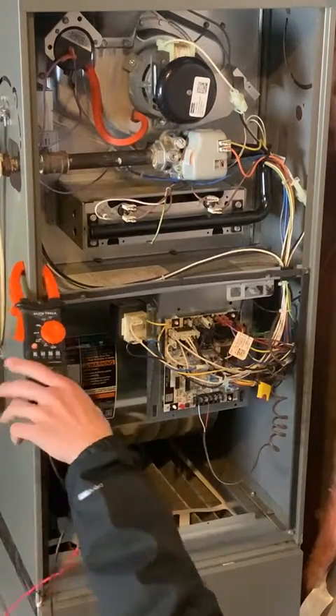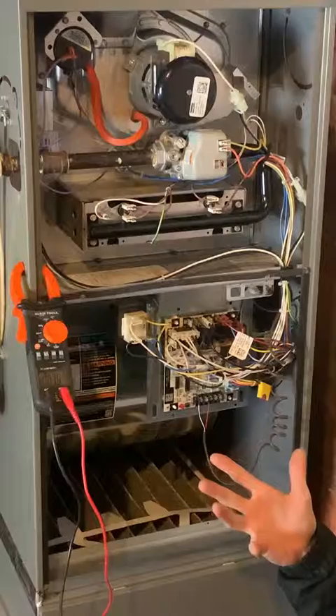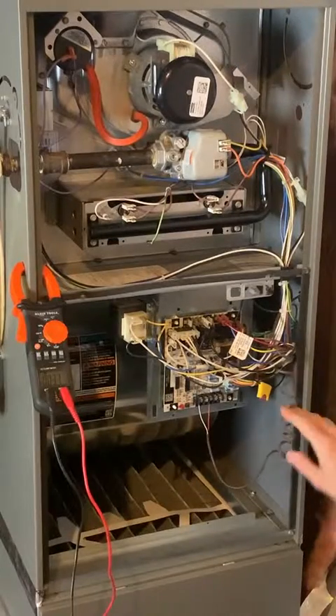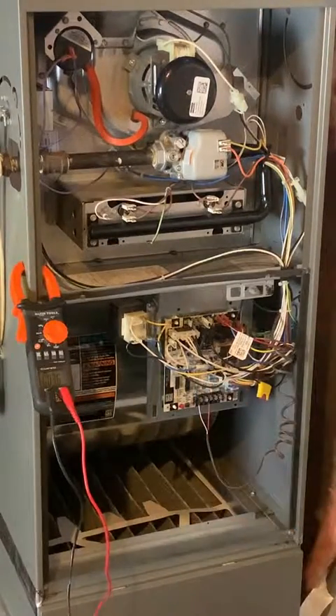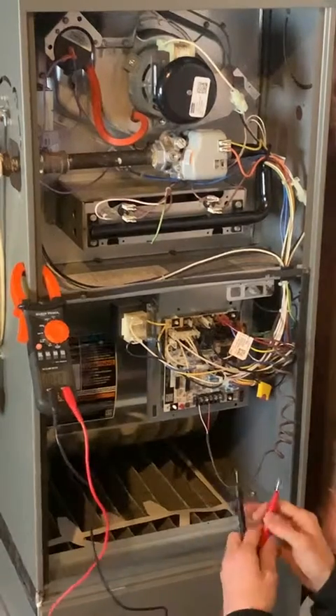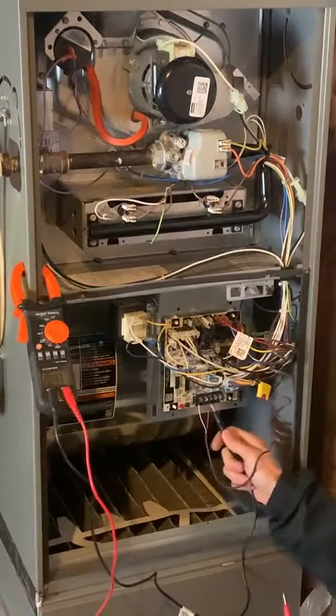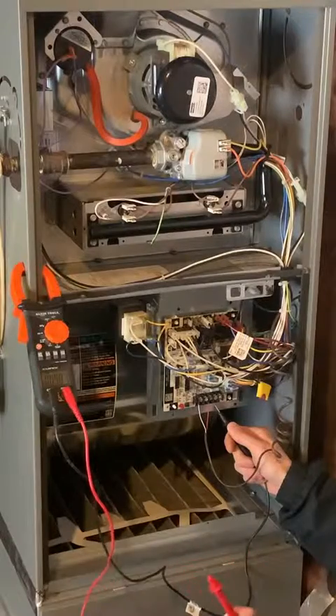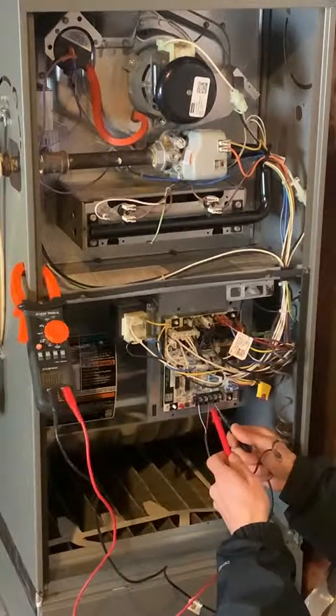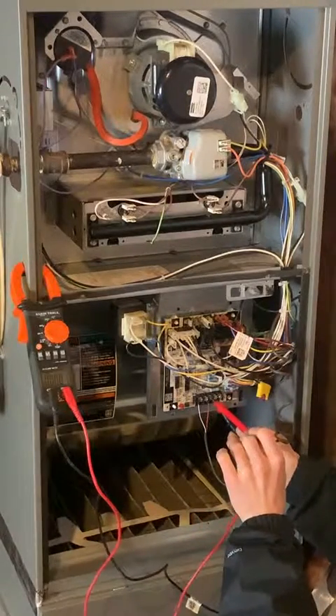If we have the thermostat set to heat, the first thing we want to check is the thermostat terminals. This is the wire that connects directly from the thermostat in the home to the control board. We're going to put one lead on common — or you could put it anywhere on bare metal within the furnace — and the other lead we'll go to the R terminal. The R terminal will always have power; it'll always read 24 volts AC as long as the furnace has power.